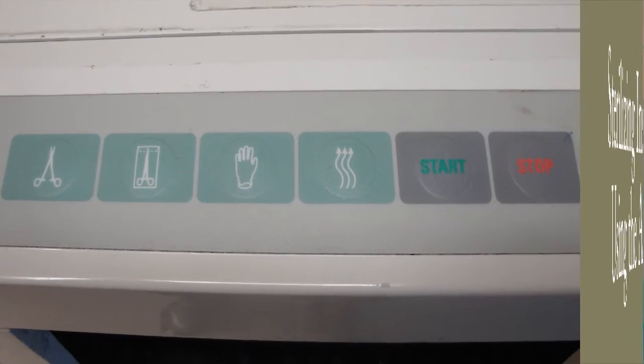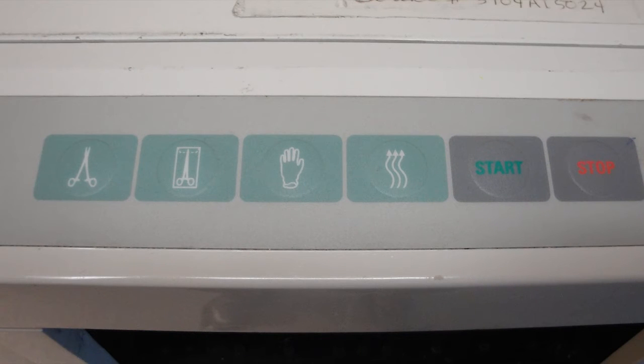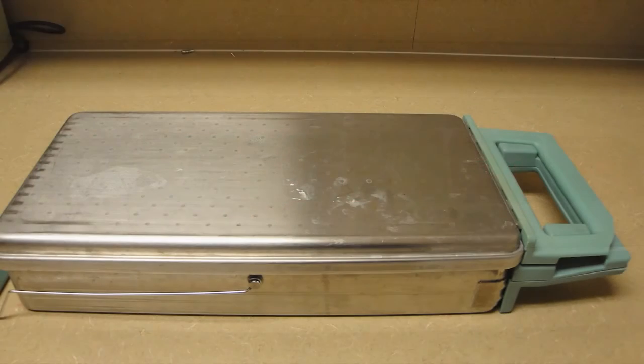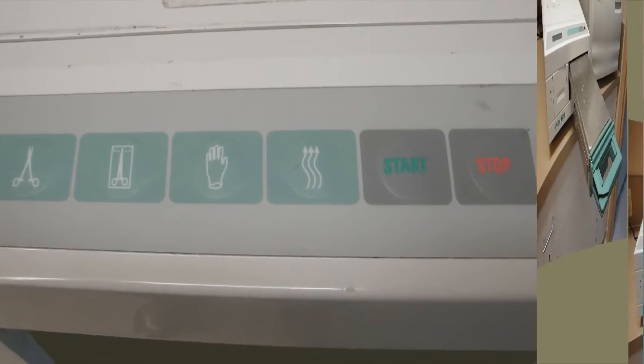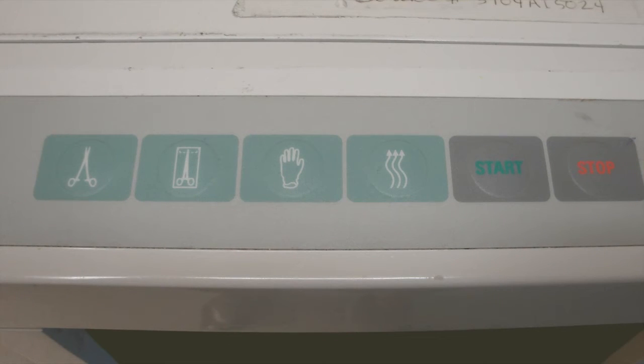You've now soaked, scrubbed, rinsed, and wrapped the instruments in preparation to be sterilized. It's now time to sterilize them. Depending on the type of wrapping you have done, wrapped or unwrapped, you will choose different settings on the autoclave. Each instrument should have by now been placed in the cassette in its wrapped or unwrapped form. The cassette slides into the opening in the front of the small autoclave as demonstrated here. Once in place, you will need to choose the proper cycle, depending on the type of wrapping present.